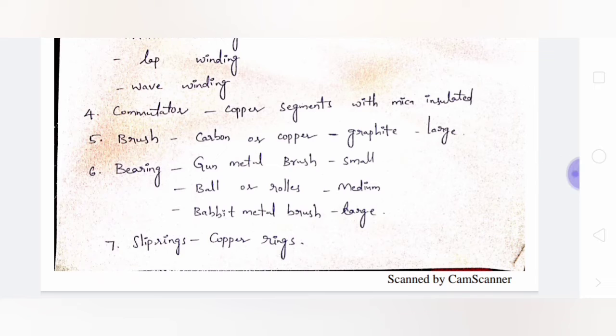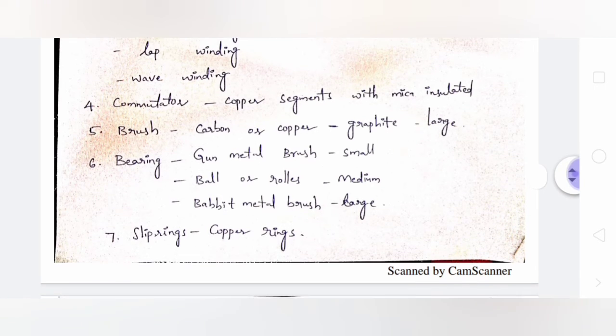Bearings are placed at the front end of the shaft and are used to allow smooth rotation of the shaft. Gunmetal bush-type bearings are used in small machines, ball or roller bearings are used in medium machines, and babbit metal bearings are used in large machines. Slip rings are made up of copper rings.